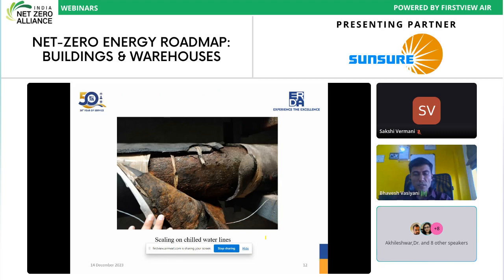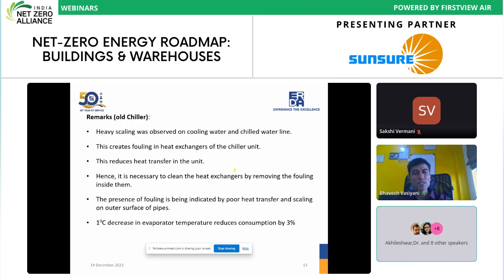So in this case, the complete circuit was studied in detail, how the chilled water is going through these lines. Line scaling was observed. It was indicated that in the condenser tubes also, the water quality and environment are not good, due to which the scaling was observed, and the cooling water temperature difference was also indicating the same. So heavy scaling was observed on the cooling water and chilled water lines. This creates fouling in the heat exchangers of the chiller unit. This reduces the heat transfer in the unit. Hence, it is necessary to clean regularly. So this should be part of the maintenance practice, that at least condenser tube cleaning should be done at an interval of at least 6 months. Now, fouling in the condenser will directly affect the power consumption of the chiller compressor.